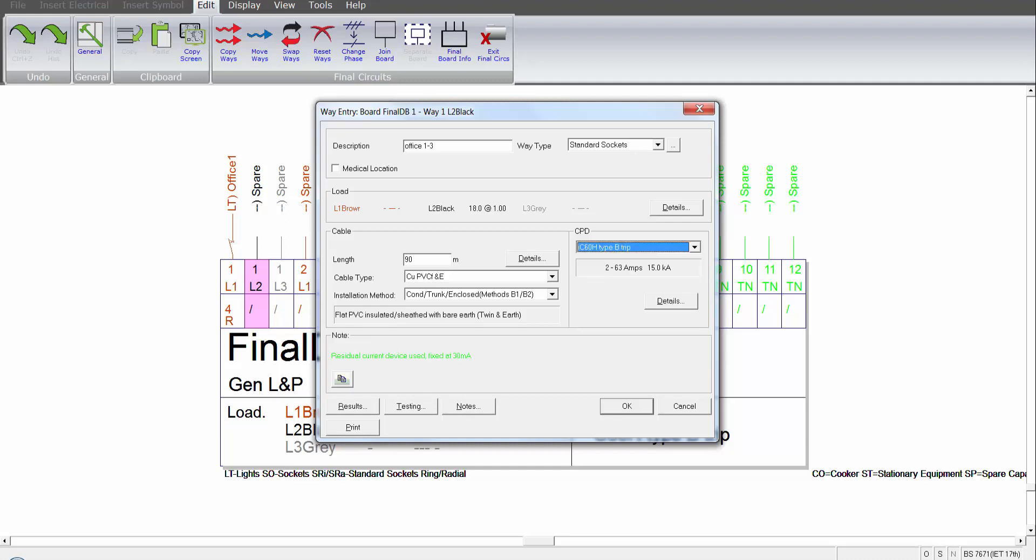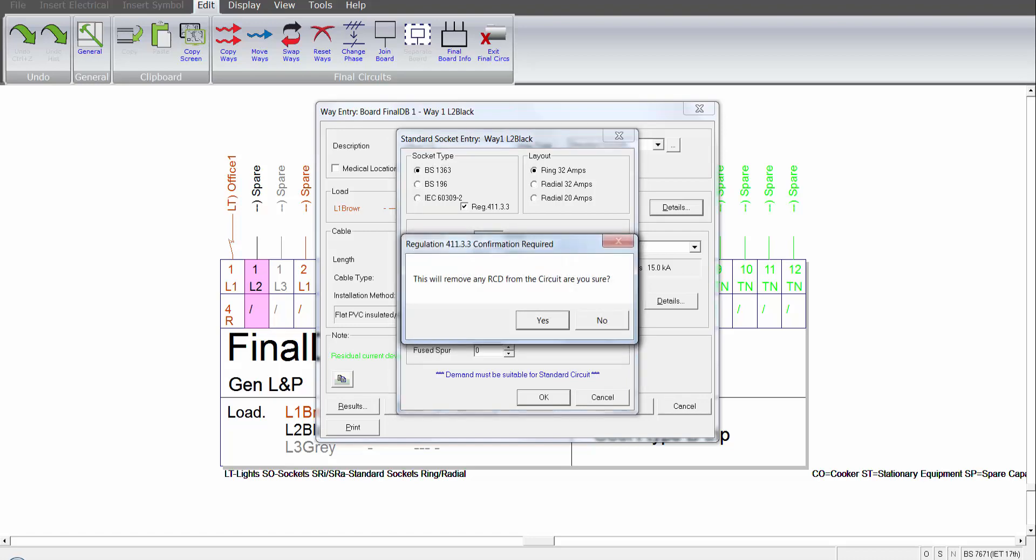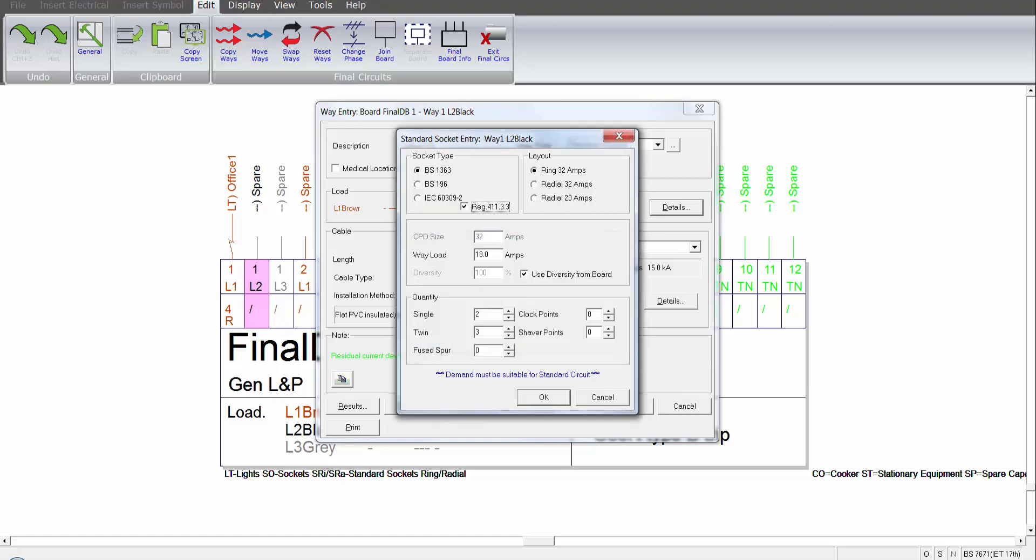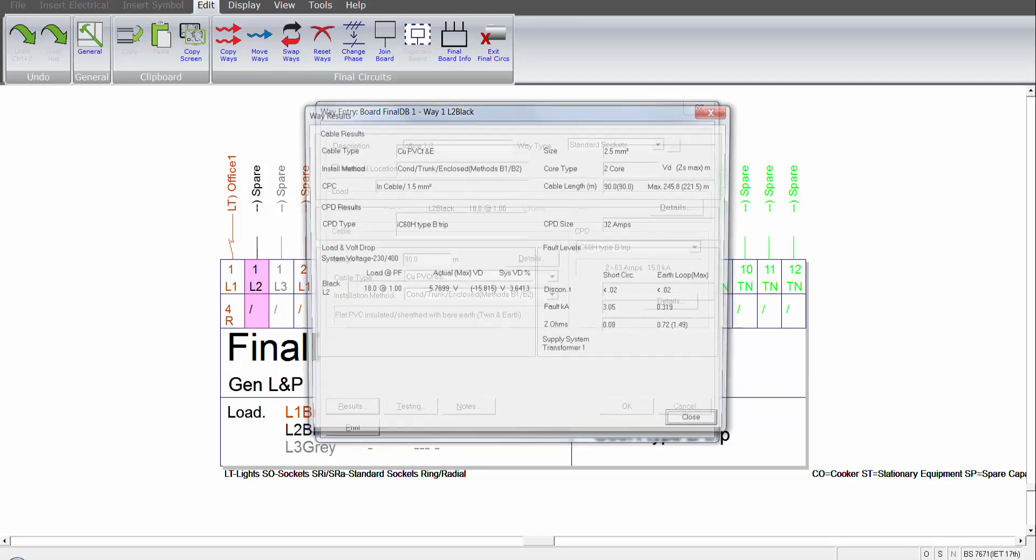And we can see here that the program has automatically taken the view as a default that this is an unsupervised circuit. We can actually remove the RCD. So if it is a supervised circuit or we apply regulation 411.3.3, if I tick that box, that will remove the RCD implying that it's actually a supervised ring main. I can then view the results.